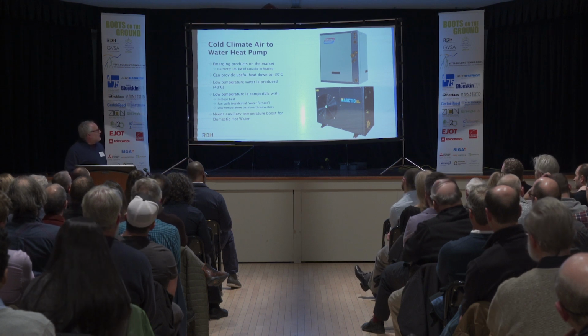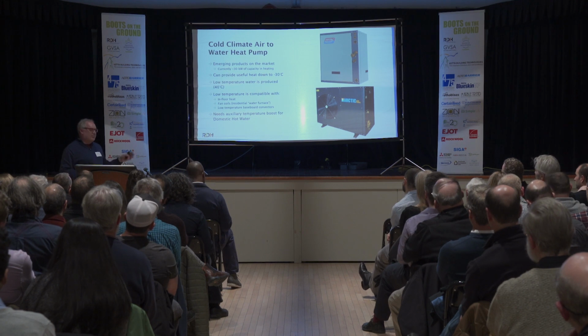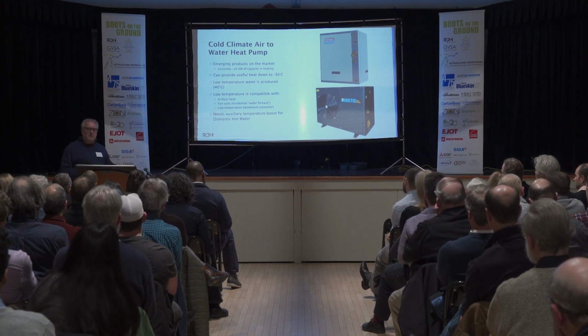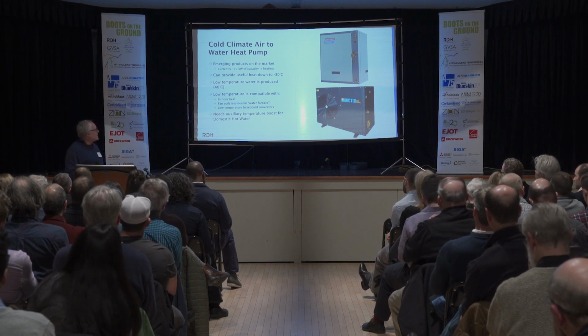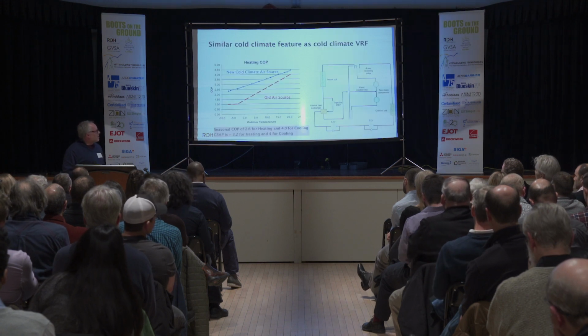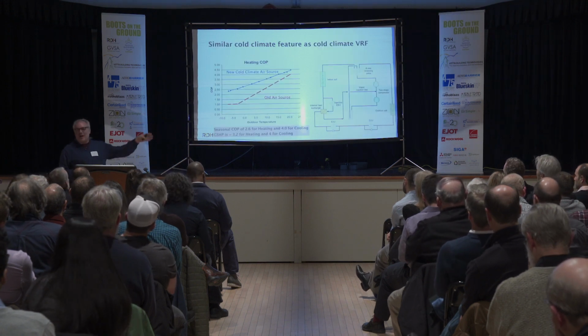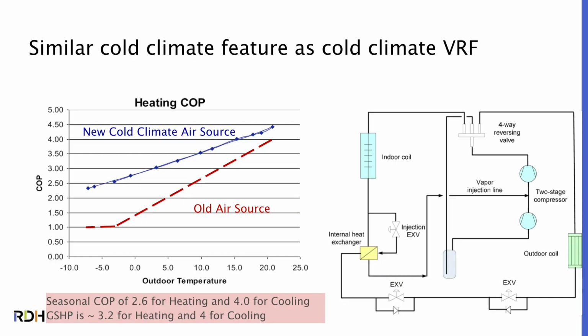They can do useful heat down to -30. They only produce 40 degrees Celsius. You're not going to use them to completely heat your domestic hot water, but they're compatible with all your domestic systems. They work the same way as cold climate VRF. It's a two-stage compressor. And so that's a nice option that's coming up.